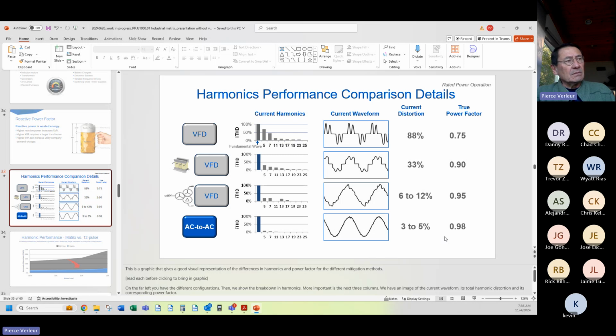Case in point, City of Lakewood, they have this beautiful SCADA system running their pumps. The City of Lakewood is a freshwater utility, supplies water to the people in the City of Lakewood. SCADA stands for Statistical Control and Data Acquisition. Their SCADA system reports everything back to screens that you can see in the main office. And when you look at the power monitors on the pumps that are running on matrix drive, they're all pegged at 0.98, regardless of what speed they're running at.